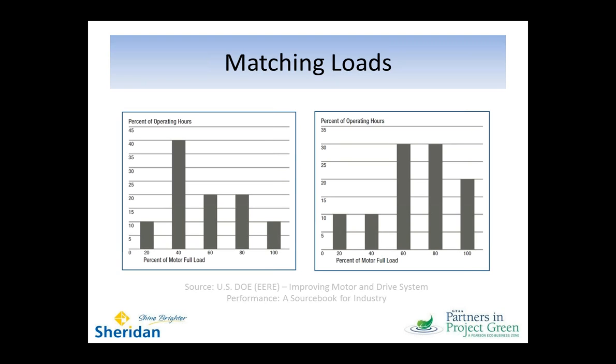In the second graph on the right, if you look closely, you see really two different operating regimes. One where the motor is at about 20 to 40% of full load, and then another where it's 60% and above. If you think back to that motor efficiency curve, remember that it was perfectly happy between 100 and 60, really 50, and that its efficiency was maintained. That might give you the idea that you can use a motor that would be happy running at two different speeds, maintaining its efficiency on the loading between 100% and 60%, but at its second speed, which is more like the 40% load, it would be perfectly happy supplying the 20% requirement at the same time. And so there are specialized motors that will run two speeds or more in some cases, and that would be the application you want to apply that to. So you're matching the motor type and the motor drive to the different load profile you see. So, an important tool for you.